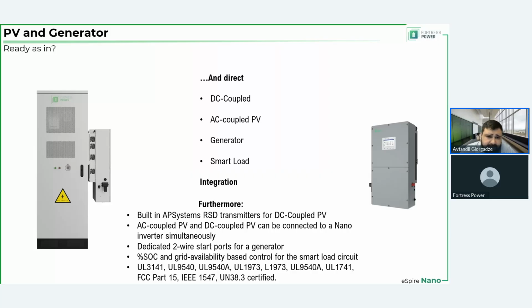Furthermore, we mentioned that it can do DC coupled PV, but that's not all. It has a built-in APS RSD transmitter for the DC coupled PV, which eliminates the extra work of putting in the transmitter. What is expected of you is just to add the receivers or MLPEs behind the electrical panels, compatible with the APS transmitter that will be built in, and that's it. Then power line communication can exist.